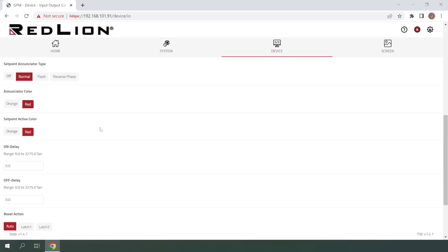The next settings we see here are the On Delay and Off Delay. On Delay is the time in seconds that the setpoint alarm is delayed from turning on after the trigger point is reached. Off Delay is the time in seconds that the setpoint alarm is delayed from turning off once the setpoint alarm is no longer being triggered. I won't be using any delays for this example, so I'll leave both of these set to their default value of zero.